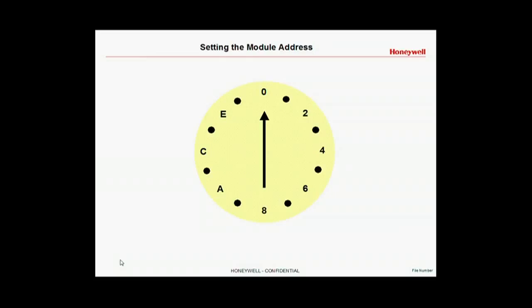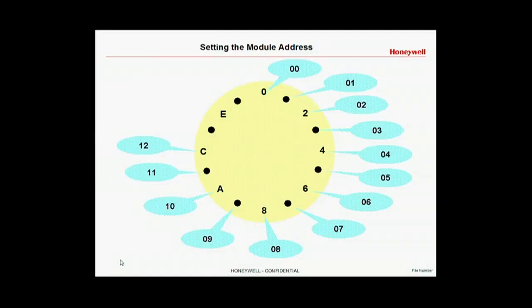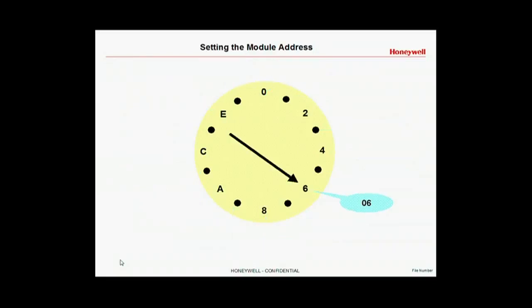The hexadecimal address selector on each of the modules is normally parked at 0. As you turn the arrow you will notice the different module addresses. Please notice the dot in the middle of each numeric number is ascending. This gives us a total of 16 valid addresses. If the arrow is turned to 6 the module address is 06.